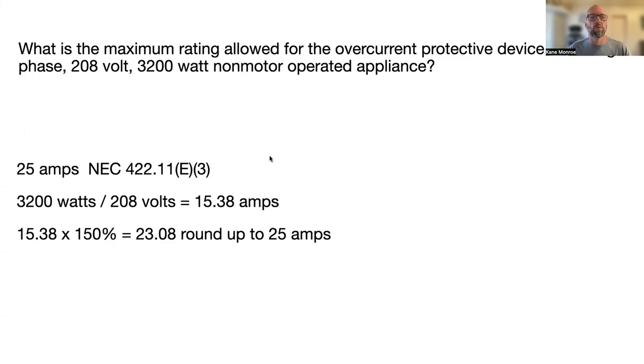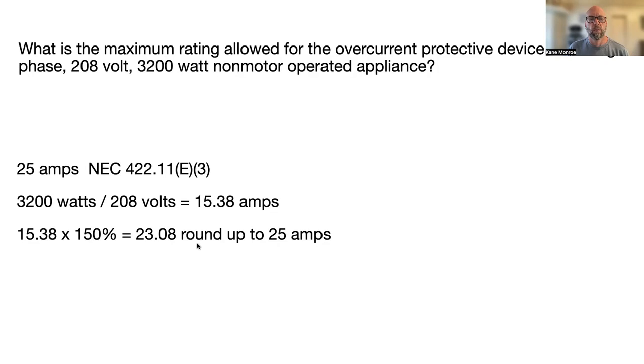We go to NEC 422.11(E)(3) and do a little Ohm's Law. We take 3200 watts divided by 208 volts, which equals 15.38 amps. Then 422.11(E)(3) tells us to take up to 150% of the non-motor-operated appliance load, giving us 23.08 amps. We round up to 25 amps because per Table 240.6(A), that is one of the standard overcurrent protection device sizes.